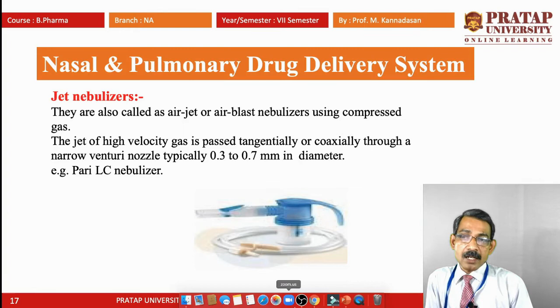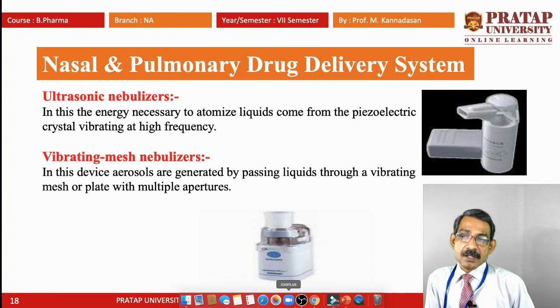Ultrasonic nebulizer: in this, the energy necessary to atomize the liquid comes from a piezoelectric crystal vibrating at high frequency. Vibrating mesh nebulizer: in this device, aerosols are generated by passing liquid through a vibrating mesh or plate with multiple apertures. In the device, there are multiple apertures in the plate, which are set to vibrate.